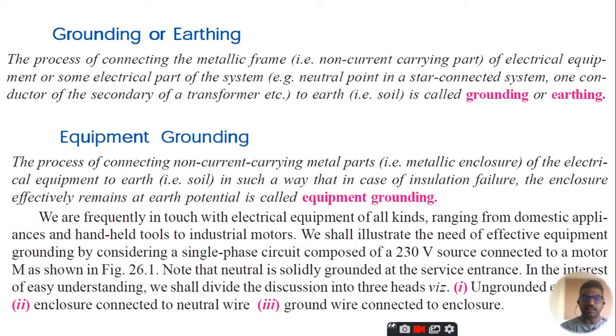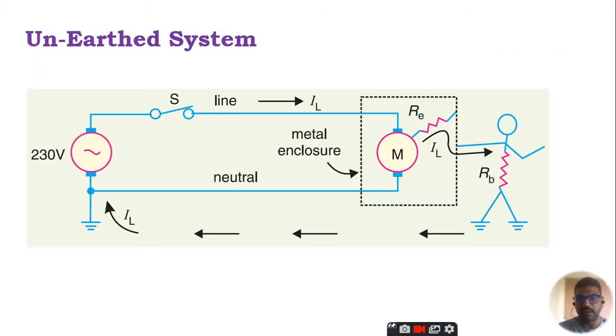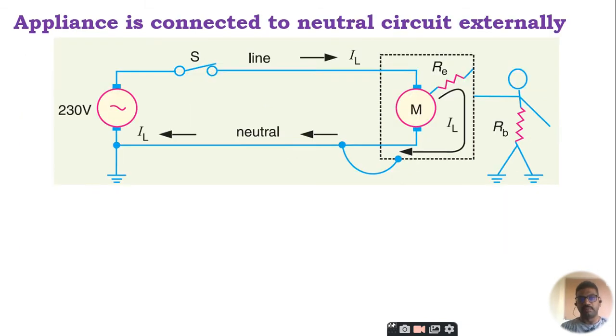In the interest of easy understanding, we shall divide this discussion into ungrounded equipment, enclosure connected with the neutral wire, and ground wire that is connected to the enclosure. So this is the unearthed system, where the earthing is not given. If a residual current may flow in the body of the equipment, then it adds the resistance of the body of the human being, and this RB represents that resistance, and RE is the equipment resistance. Though it is in a metal enclosure, if we unintentionally come in contact with certain equipment, then we also feel a shock. That is what we call an unearthed system.